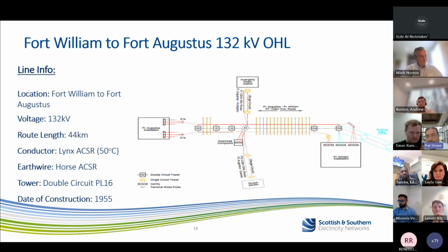In Fort William, the challenge was not only to increase the capacity of the line, because the smelter, a major customer at the far end, was looking to expand, and also to safeguard jobs for a new investor. But also, because it's radial without a backfeed, we had to reconductor the line with one circuit live, and be able to put supplies back on in an emergency, otherwise the aluminium would go off in the machines in the smelter, and that would be the end of the smelter. So quite a few challenges, as you can imagine.